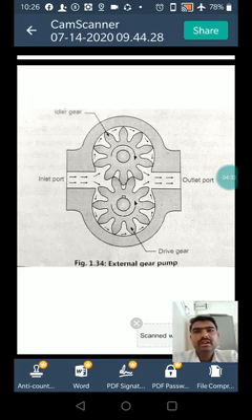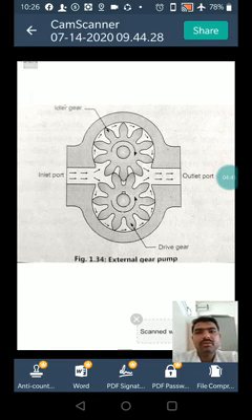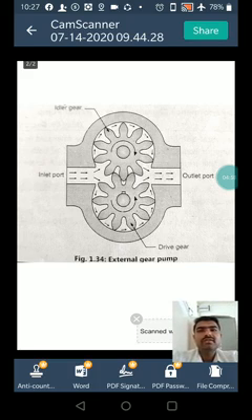Most of the liquid carried is discharged towards the delivery side, while a small quantity of liquid returns to the suction side. The delivery side remains separate from the suction side through the flanks of the meshing teeth and the casing of the pump, which is close-fitting to minimize leakage of liquid.